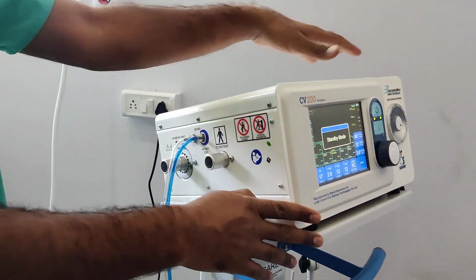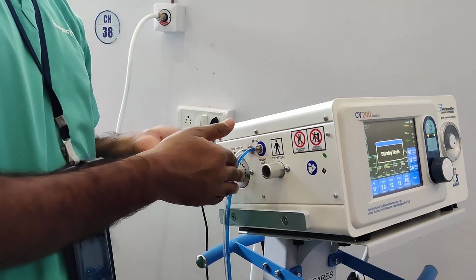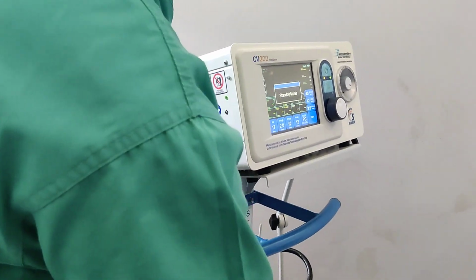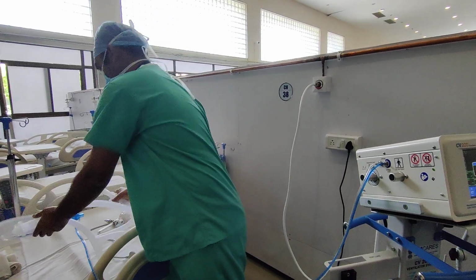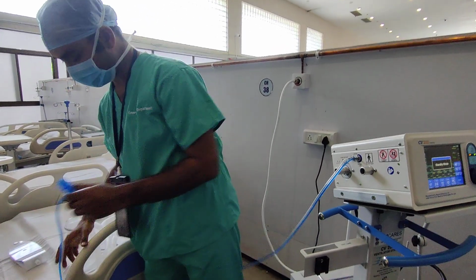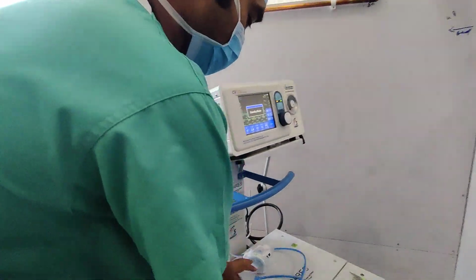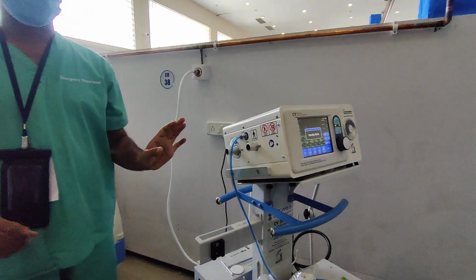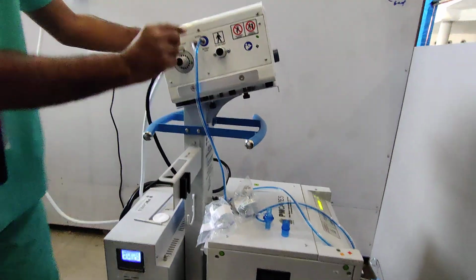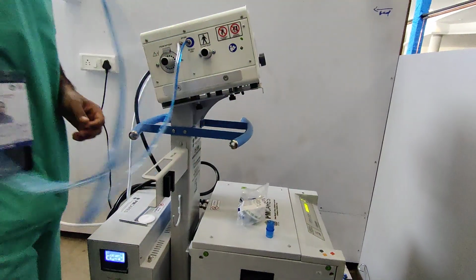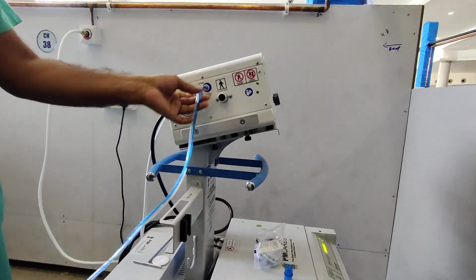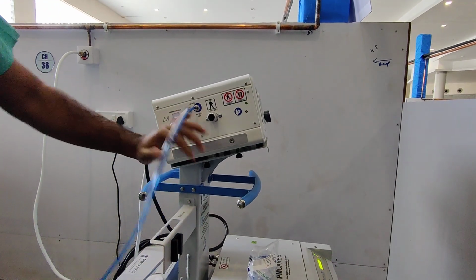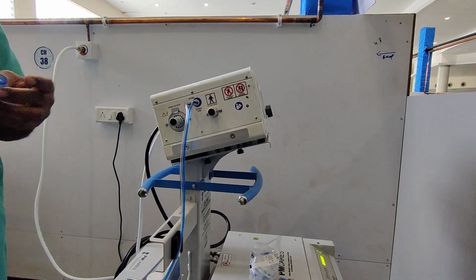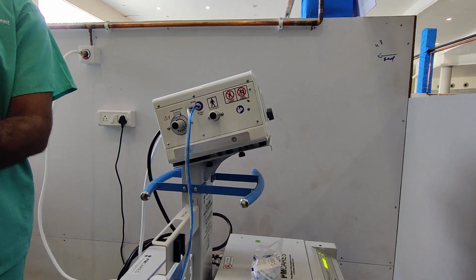Once you've selected the mode, you can connect the circuit before or after selecting your mode. So this is your ventilatory circuit. As Tapan was telling about the sensor, I will show you each and everything separately. So this is your ventilator. Usually you will find this kind of thing. So this is your sensors. This is your sensor tubings. One is blue and another one is white, and this is a connector at patient end. Usually it's written here patient side. So this blue tubing should go towards patient, and this should go towards ventilator side.